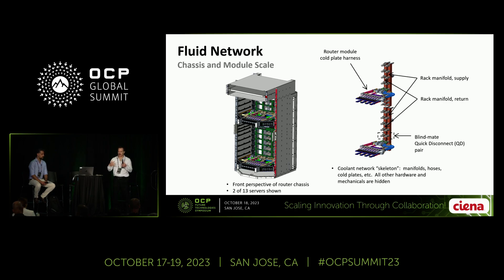Zooming in now to the Ciena equipment — this is our coherent router. I'm showing a chassis on the left. Two of these chassis can fit into one rack, providing 128 terabits per second of packet switching. I'm showing two router modules of 13 possible modules that can insert into the rack. From the user's perspective, the modules plug in and extract normally — the user doesn't need to think about anything. But what's happening at the rear of the module is that we're simultaneously making an electrical connection and a fluid connection. The fluid connection is done through a pair of blind-mate quick disconnects, which are floating to accommodate mechanical tolerances.